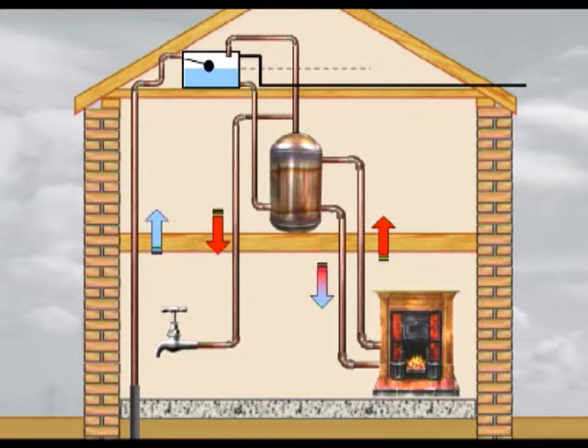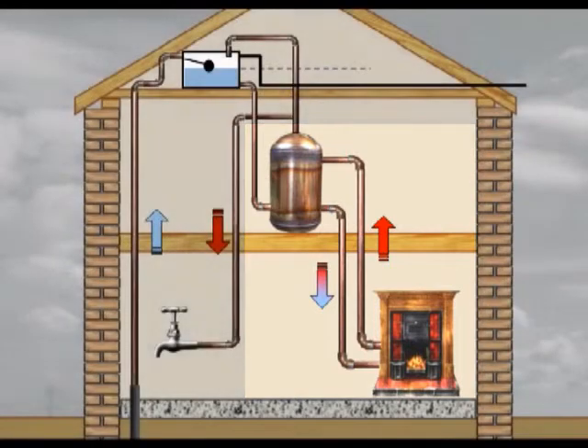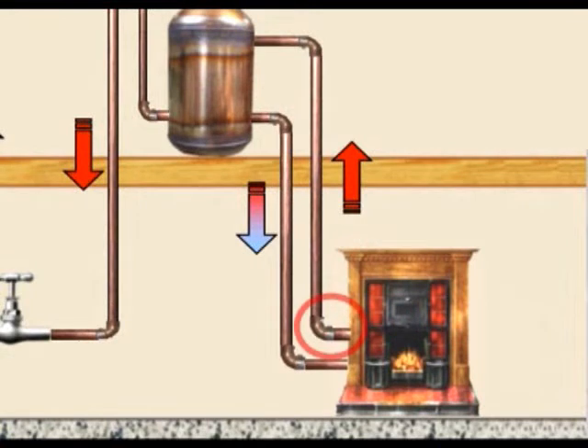As hot water is drawn through the taps, fresh water is fed to the bottom of the cylinder from the tank in the roof. This water then slowly circulates through the boiler and back to the top of the cylinder. This means that the water coming out of the taps has been heated directly by the back boiler. It could sometimes be tainted with particles of rust inside the boiler. More serious was the risk of limescale deposits. These occurred in hard water areas and led to furring of the pipes, reduced flows and even blockage. Furring was worst where the pipe was hottest.